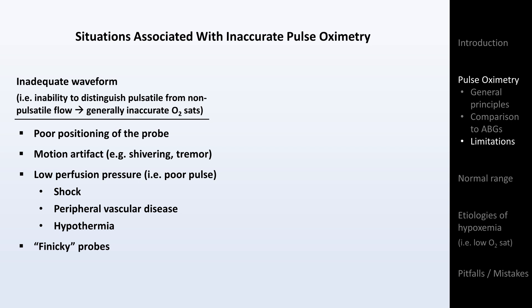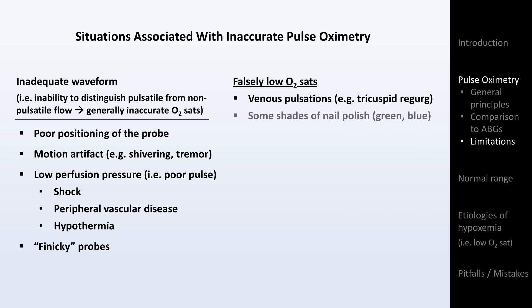Situations that lead to false low O2 sats include prominent venous pulsations, which can result in some of the low venous oxygen saturation influencing the pulse ox reading. This can be seen with severe tricuspid regurgitation. Some shades of nail polish can also impact the pulse ox, particularly green and blue. If this is the case, problems can be averted by placing the pulse ox probe on the finger sideways.